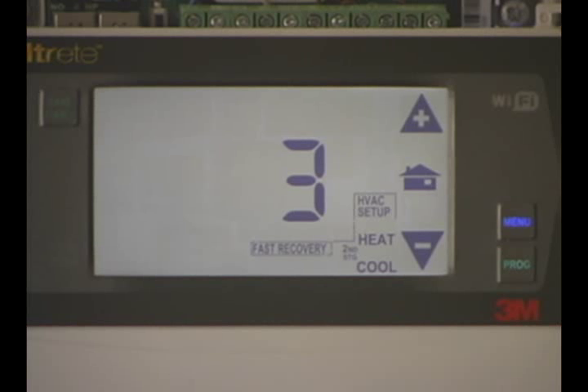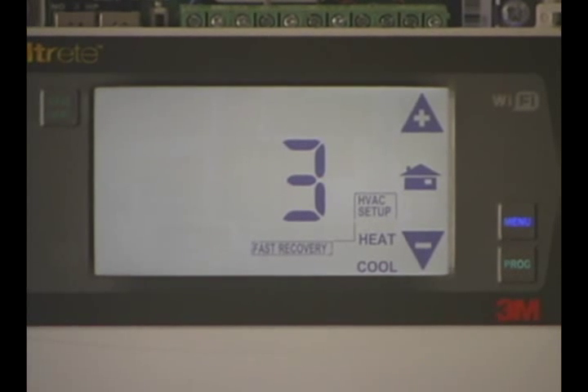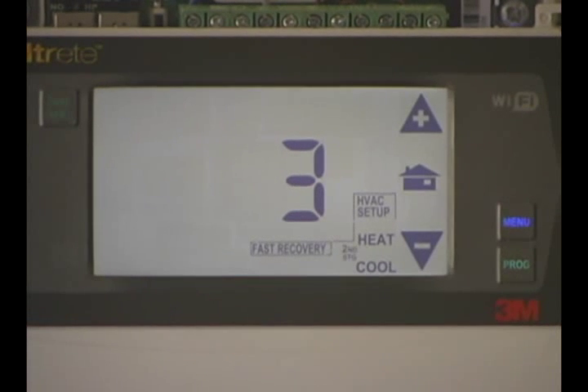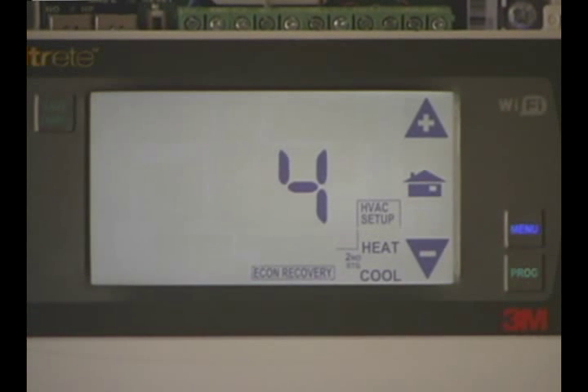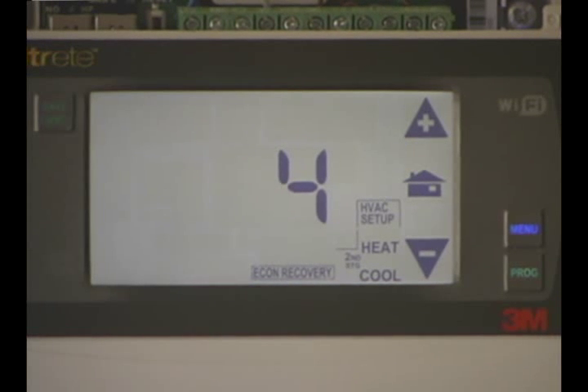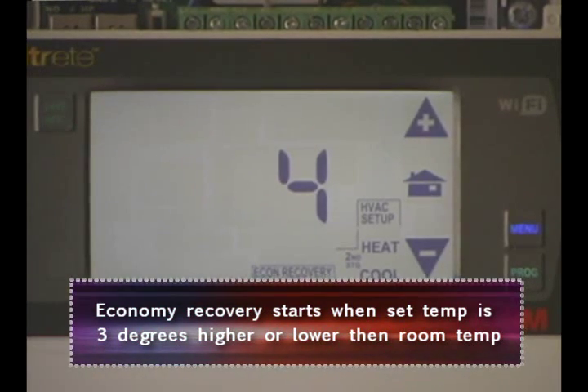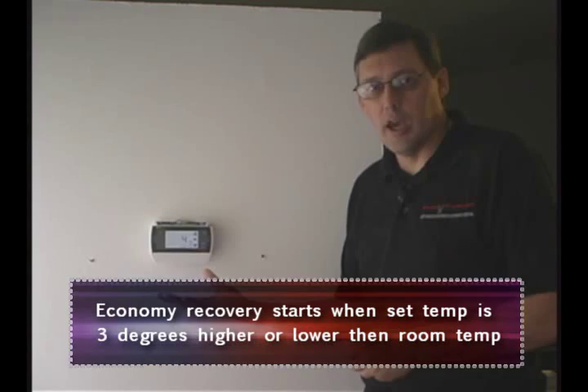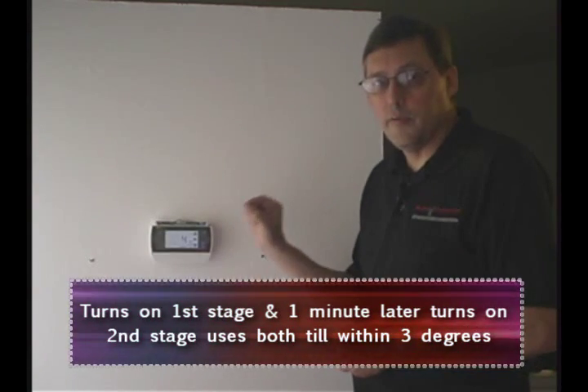If you go to number 3, the 2 is flashing beside the heat and cool, meaning we have 2 stages of heat and 2 stages of cool. Number 4 shows economy recovery with the 2 solid — so we're back to 1 stage of cool and 2 stages of heat, but when the 2nd stage of heat turns on, once the differential is reached, it turns off the 2nd stage and only runs the 1st stage until we reach the desired set temperature.